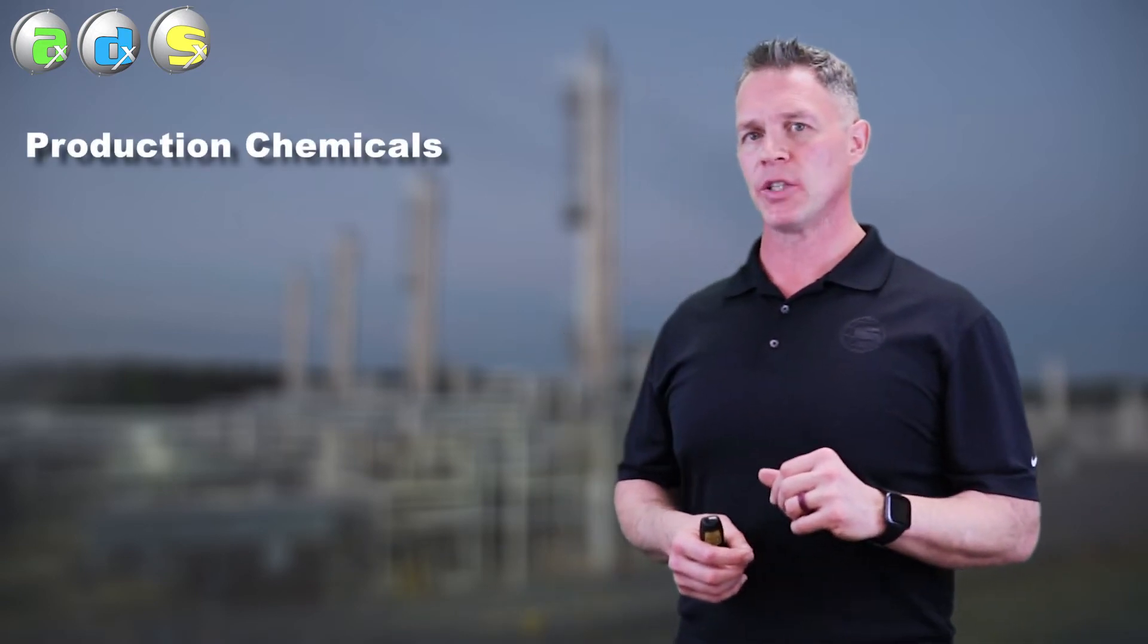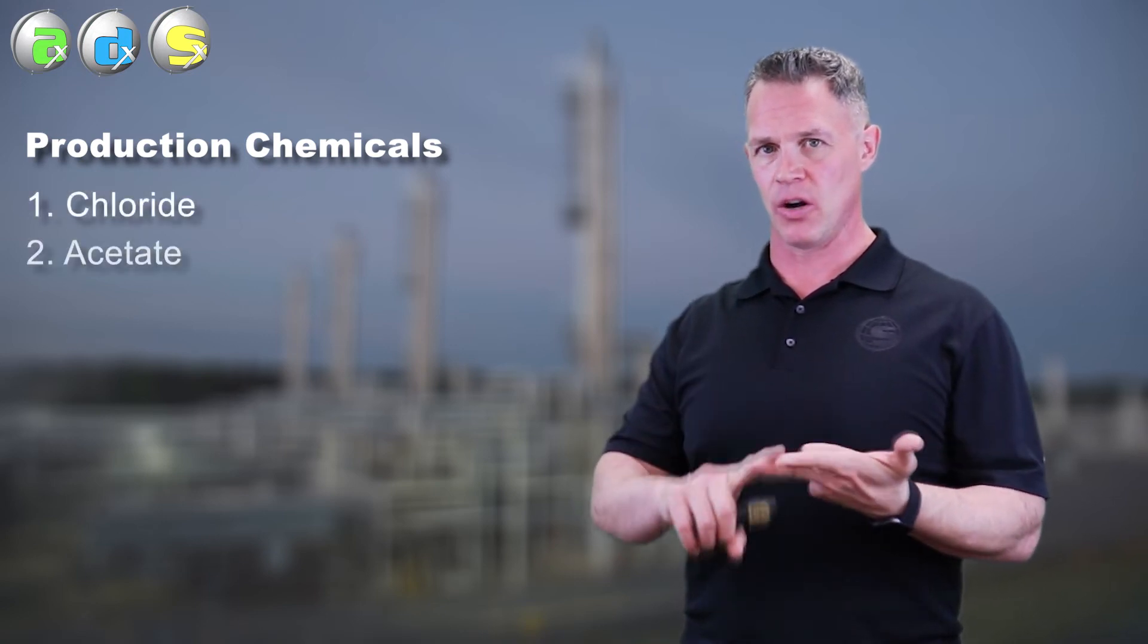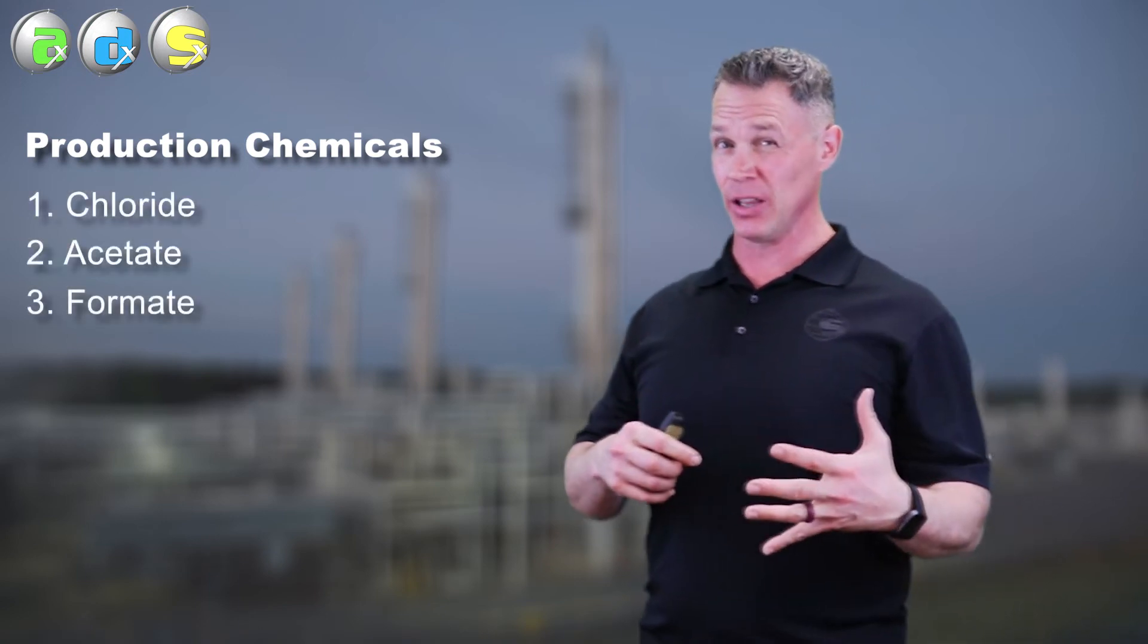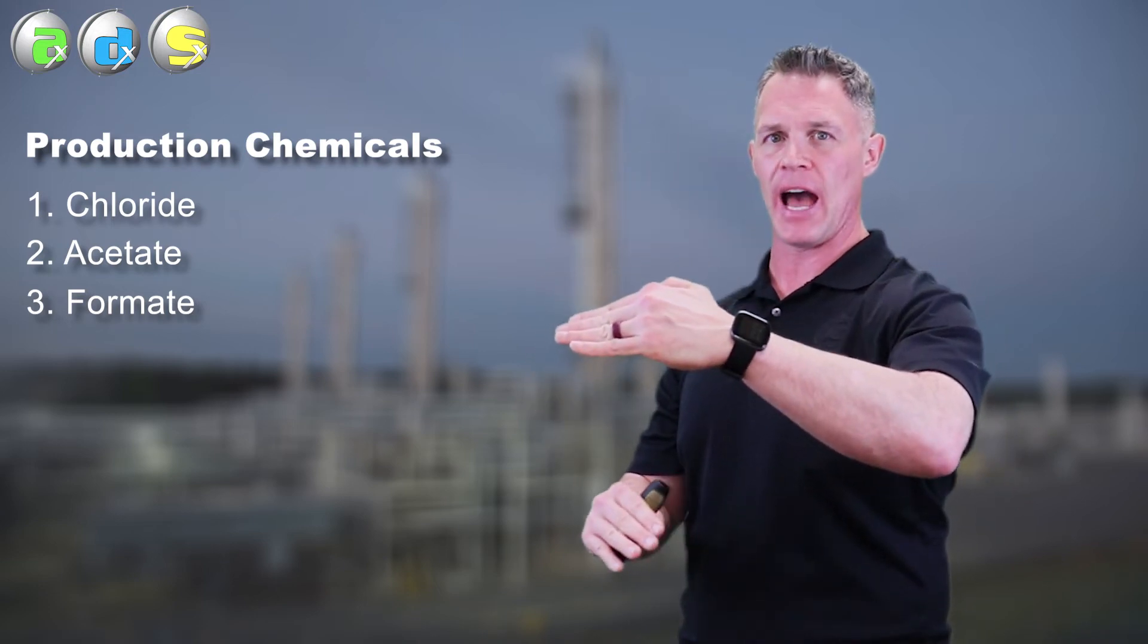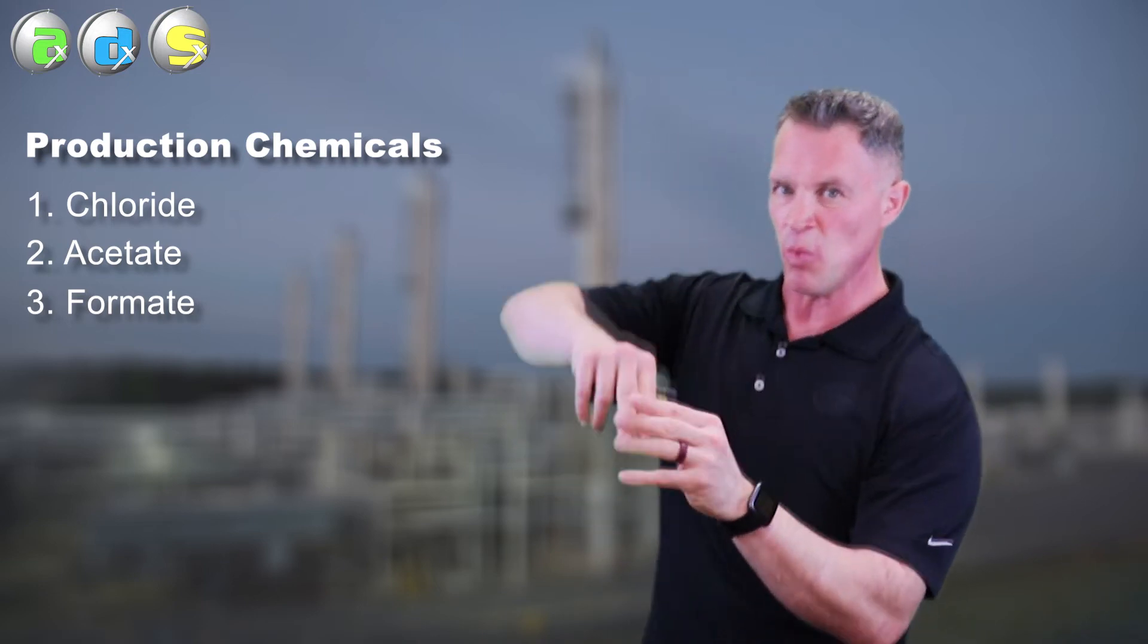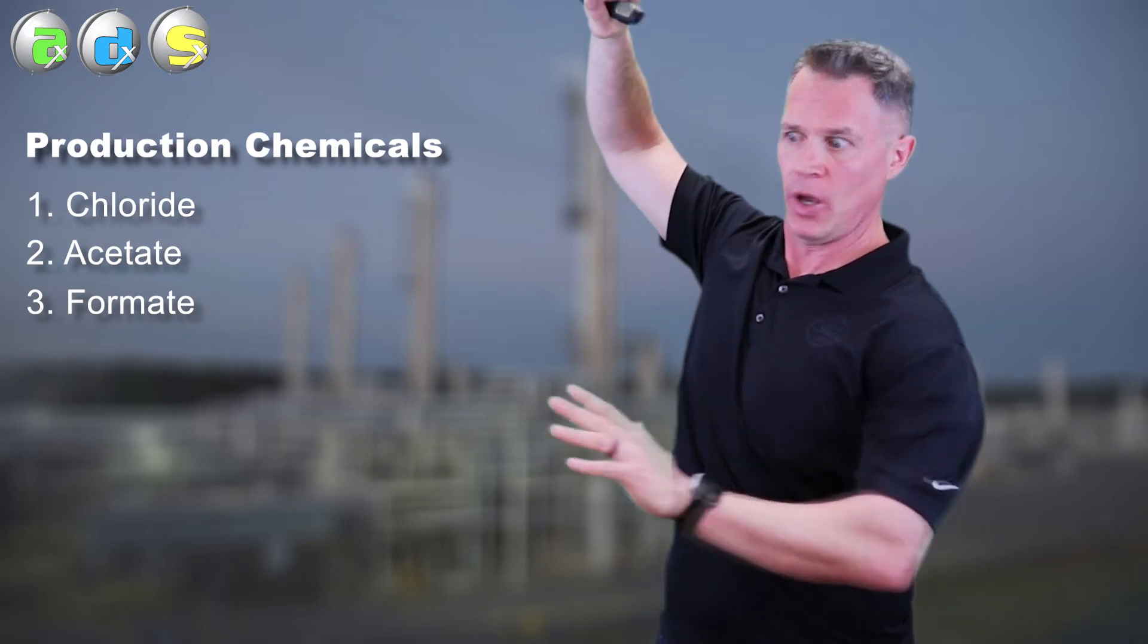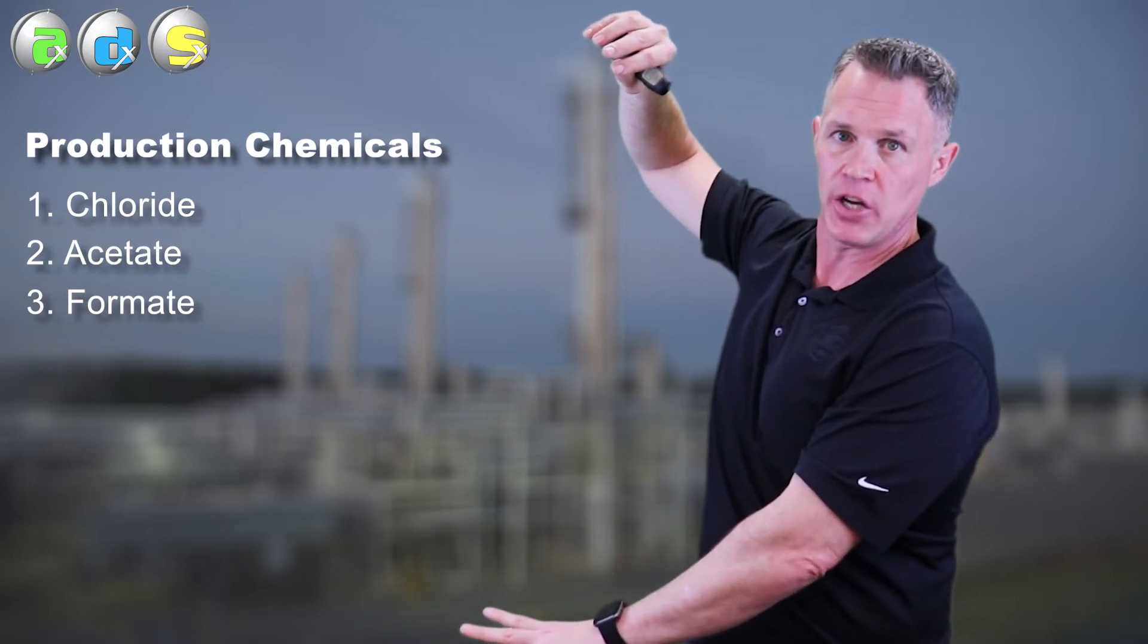Another contaminant which can cause heat stable amine salts are production chemicals or pipeline chemicals. The most common ones we see from this type of contamination would be chlorides, acetate, or formate. But what you're really looking for is in your list of acid anions that you got from the lab, if you're seeing a spike in only one anion, and all the rest stayed low or unchanged.